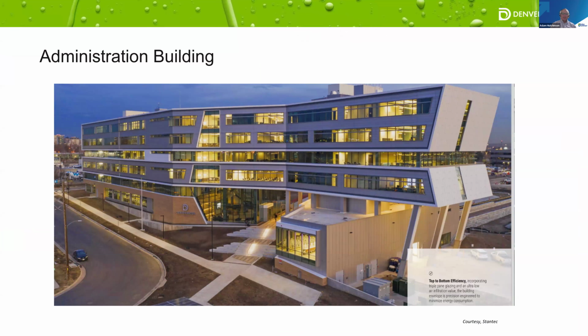I'll give you a breakdown of how we present this story. The Water Admin Building is LEED certified office space, and it has a networked lighting control system that's BACnet integrated with the building automation system. So our lighting control system and our building automation system are BACnet linked together, and they share the occupancy sensors from the lighting system, giving real-time status of occupancy in the space. This is the case for almost every single space in the building.